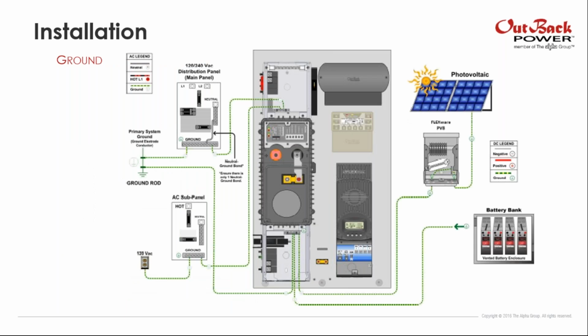So, the wiring of ground. As I said before, every OutBack power device has its own terminal block or bus bar for grounding. Everything is identified by the symbol of grounding, this one. So everything you need to do is to connect all the devices at the same port and then to the primary ground system. It is really, really easy.